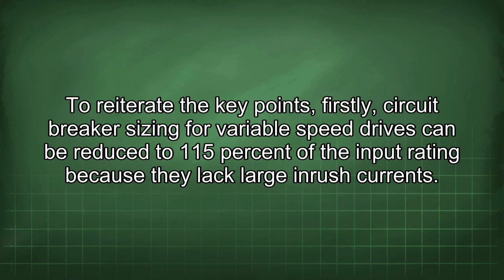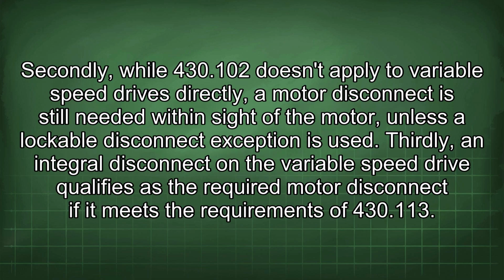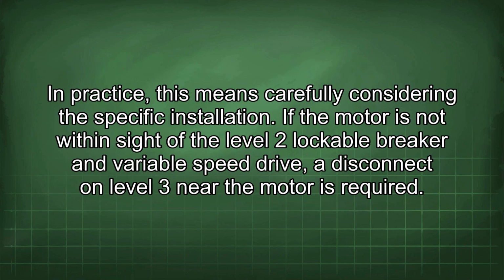To reiterate the key points, firstly, circuit breaker sizing for variable speed drives can be reduced to 115% of the input rating because they lack large inrush currents. Secondly, while 430.102 doesn't apply to variable speed drives directly, a motor disconnect is still needed within sight of the motor, unless a lockable disconnect exception is used. Thirdly, an integral disconnect on the variable speed drive qualifies as the required motor disconnect if it meets the requirements of 430.113. In practice, this means carefully considering the specific installation.